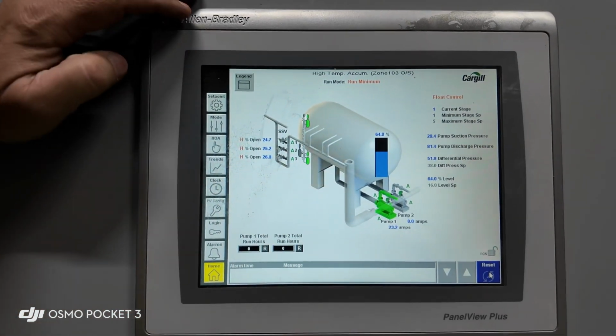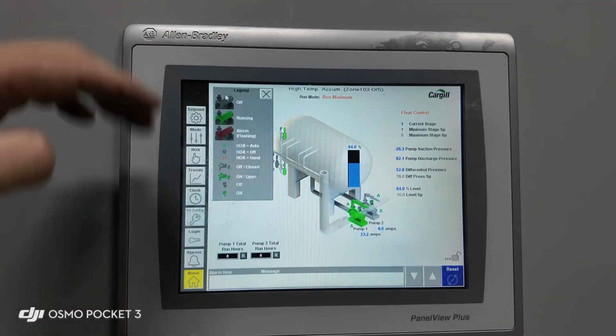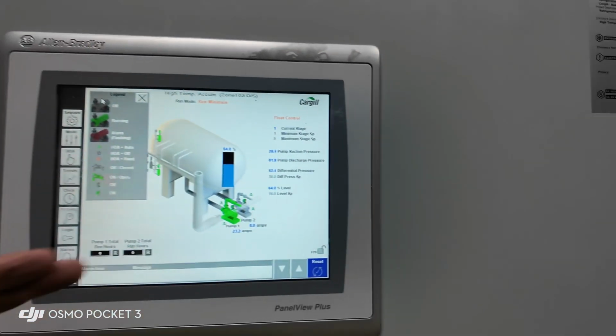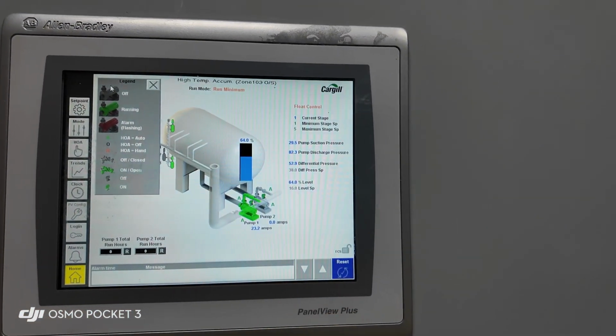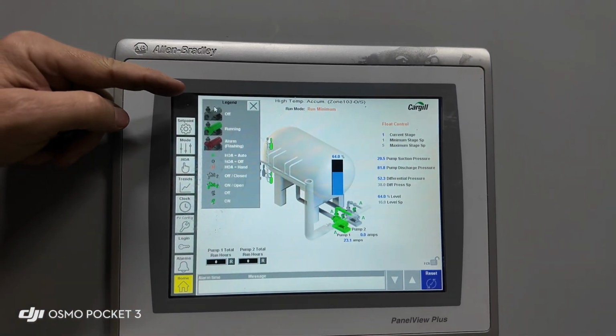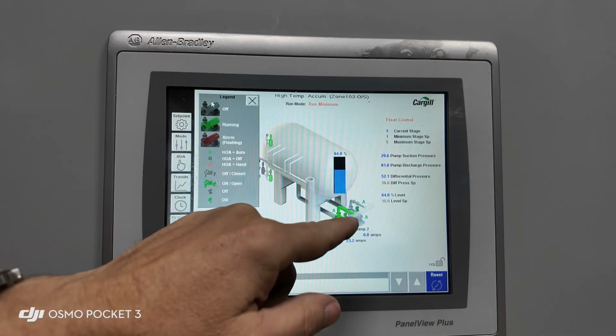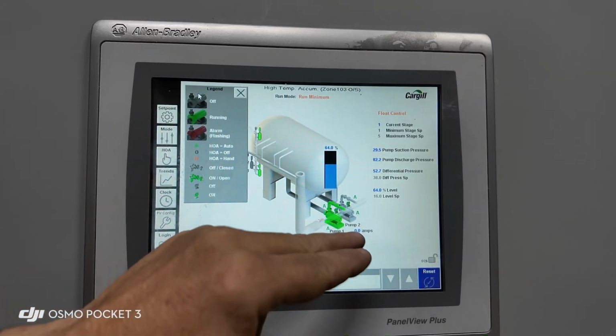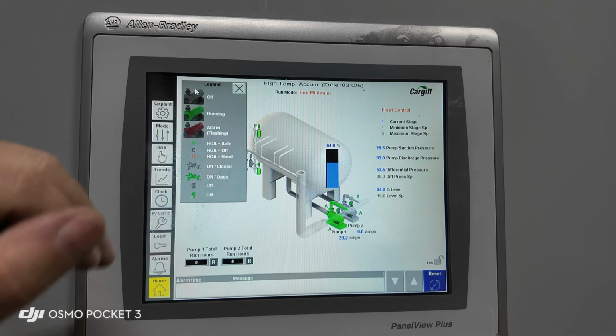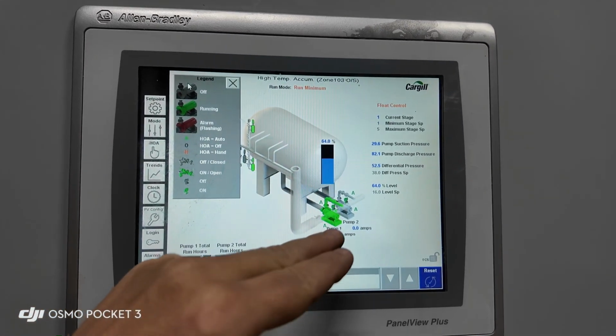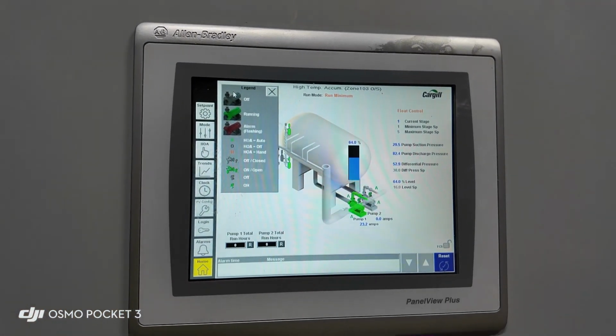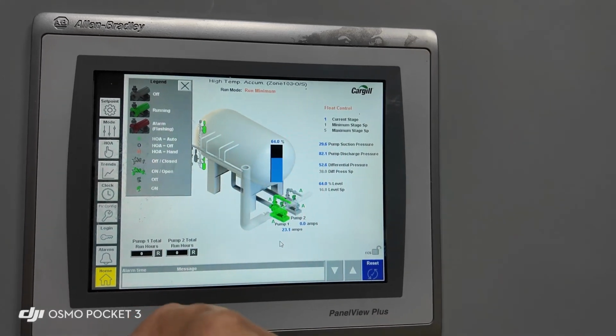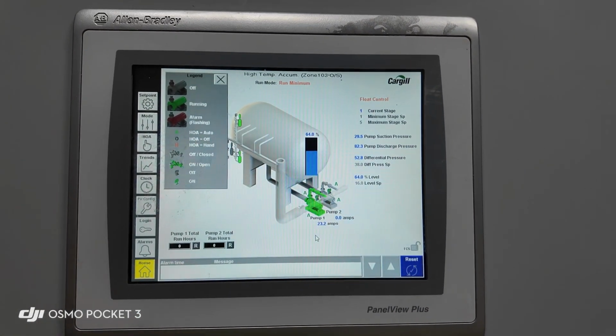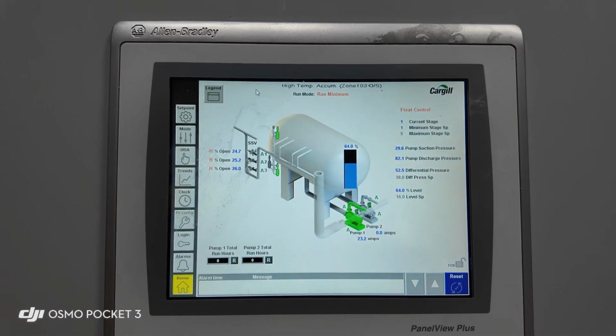We're logged in at the highest level right now, but anybody can access this screen and the legends, reset alarms. The legend shows what's going on. A's are for automatic, M's for manual, O's for off. Those are for solenoid valves. Green on the pump means that it is pumping. It's doing good. We have a pump amps indicator on each pump. Okay. We can simply close the legend button there.